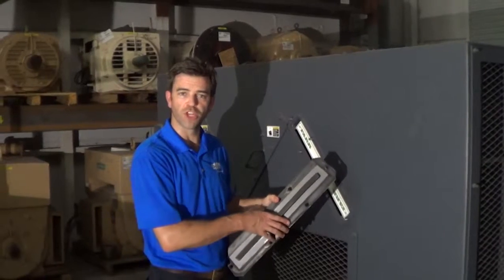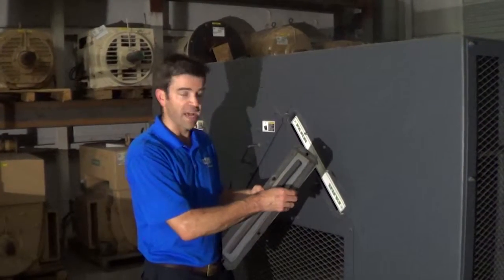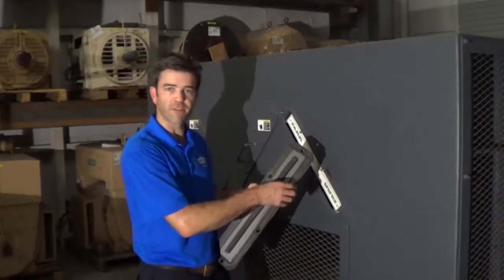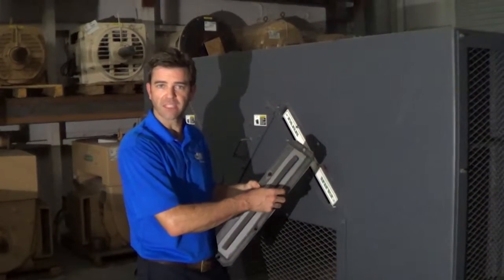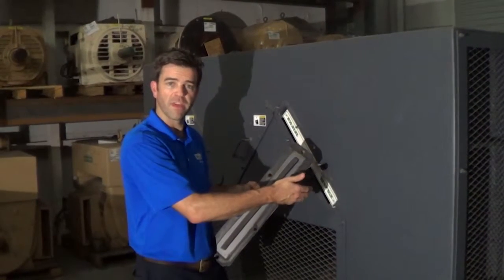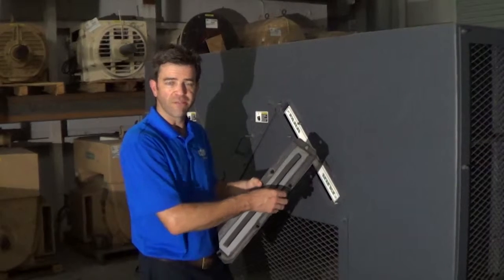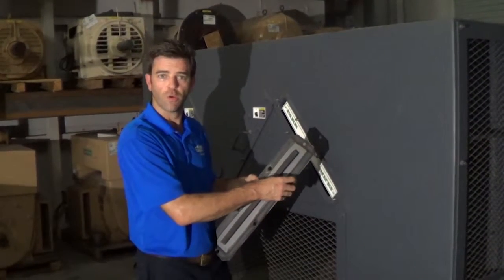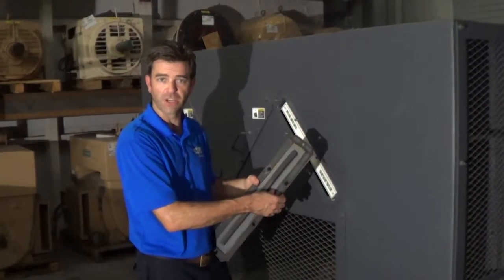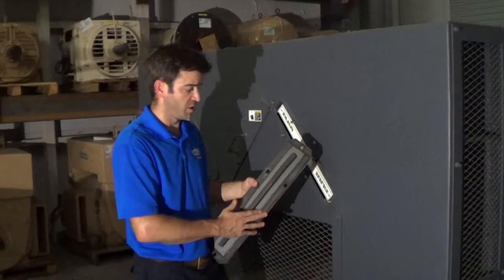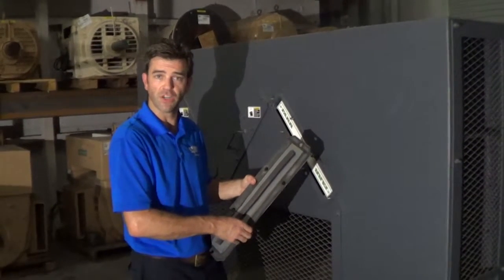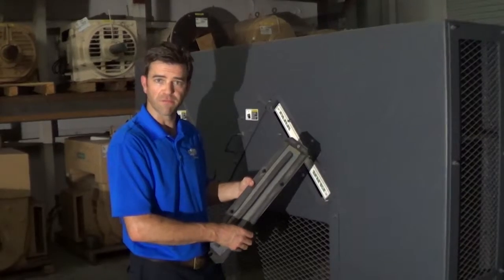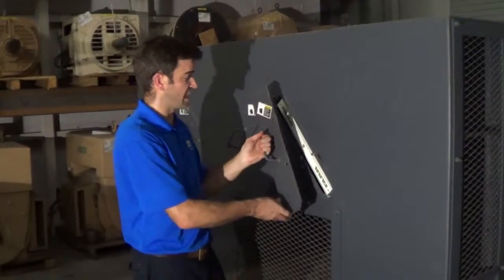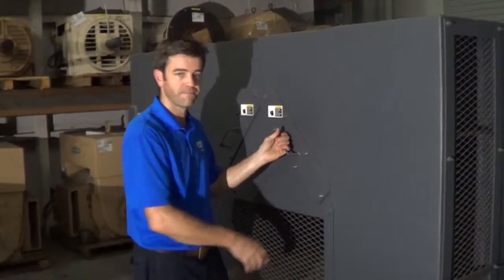Another common problem with enclosures and covers is the gasket material. When removing different covers, it's common for the gasket material to stick, some on the motor and some on the cover. If the gasket material tears, replace it with neoprene or Viton. If the gasket material is in good condition and is simply peeled off, use some spray adhesive to reattach it to prevent leakage into the machine.